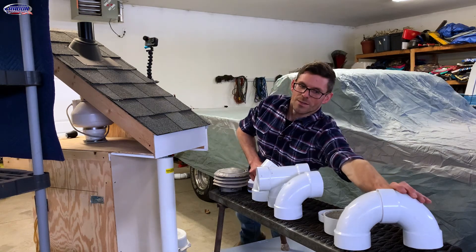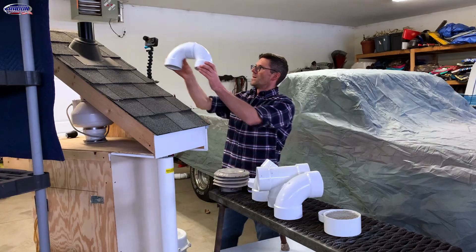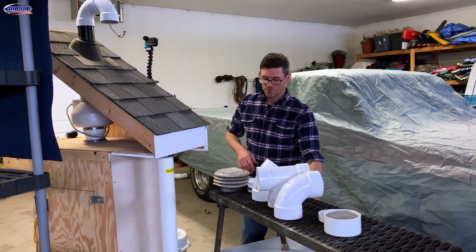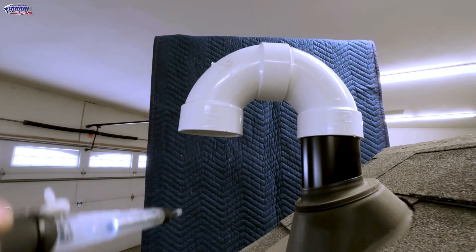Our last fitting is a U-turn shape, where it blows air straight down. This is not allowed. I can feel that wind blowing all over the roof here — it's blowing straight down onto the roof.